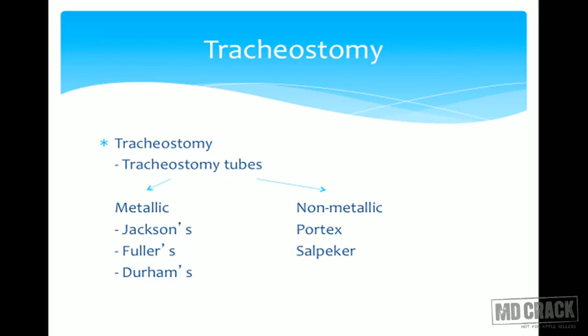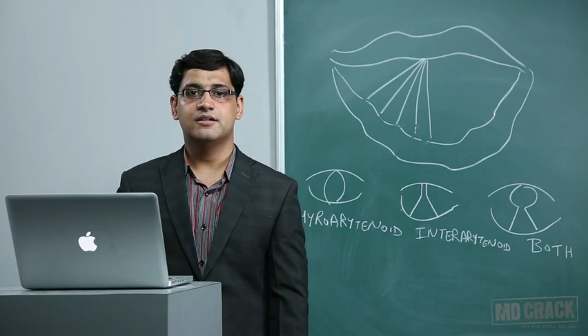Now the benefits of the metallic tube over the non-metallic tube are that metallic tubes are cheaper, easily available, and they have 2 parts, an inner tube and an outer tube, so they are easily cleaned. But the disadvantage is that they do not have a cuff, so they are not suitable when intermittent positive pressure ventilation is required. And the cuffed tubes are used for high volume, low pressure IPPV, that is intermittent positive pressure ventilation. With this we conclude this session.